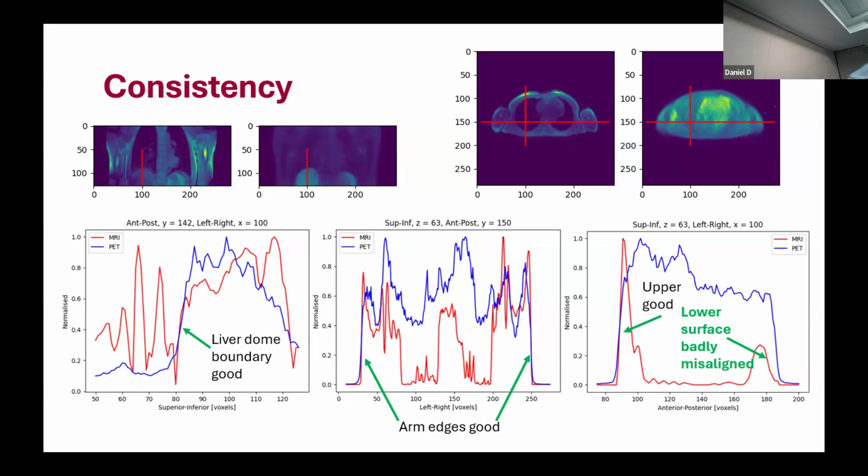And I wonder if this is what's happening with your lower boundary. Maybe the MR is a bit further looking into the patient table. Yeah. Okay. No, I haven't done anything to take account of any effects of the table, and that's possibly worth looking into. Yeah, it might just be that the patient MR AC that's performed erroneously considers part of the table as part of the patient. But I don't know. That's just something that happened to me. Okay, I will look into that.